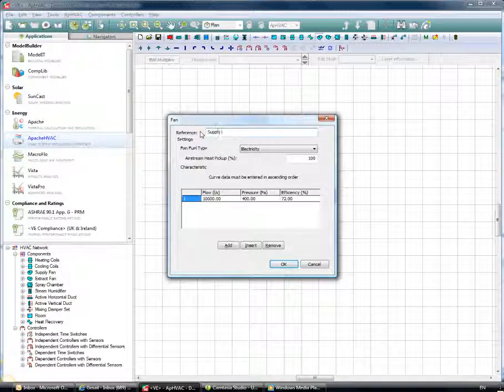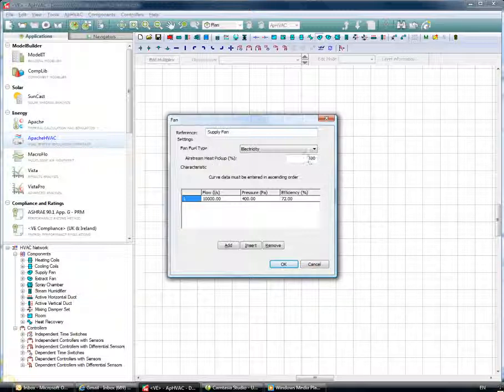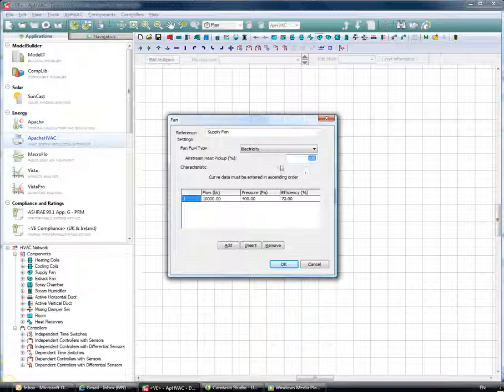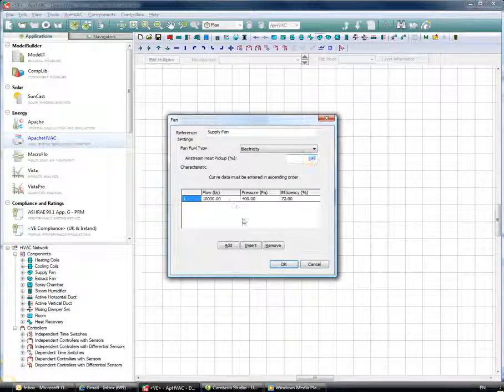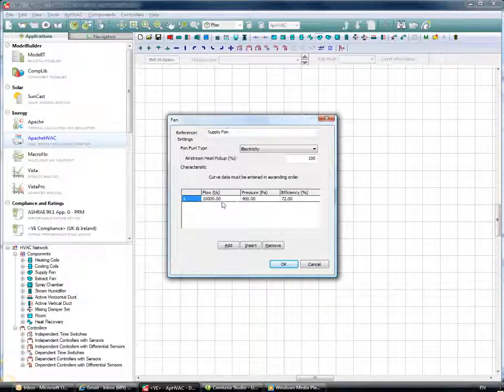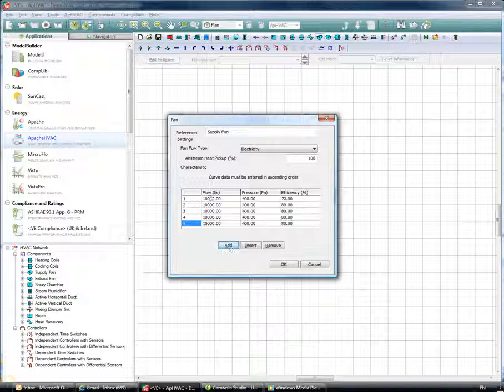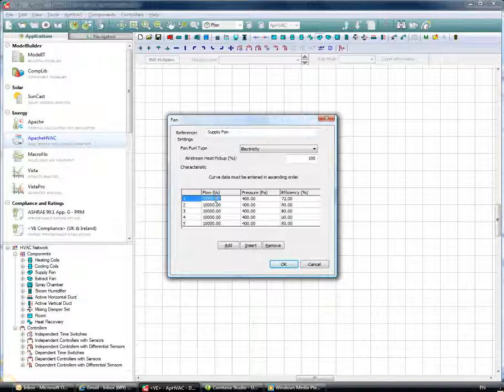I'll call this the supply fan. As I set it as a supply fan, I can go in and choose the amount of airstream heat pickup — in many cases the fan will be in-line with the airstream, so you'll typically have an airstream heat pickup of about 100%. You can also add in your fan curve data, entering it in ascending order with about five points on the curve, putting in the flow rates.